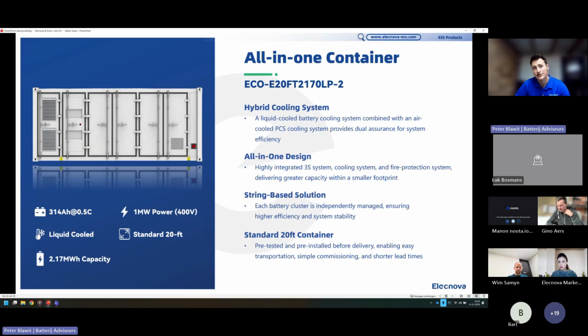Then there's the all-in-one container, bigger solutions we see more and more of. It's a 20 feet container with 1 megawatt of power at 400 volts, which is nice since a lot of current systems run at 690 volts, not really standard in Europe. The containers have about 2.1 megawatt hours of capacity, and they're liquid cooled, which is good for the systems and means less maintenance.